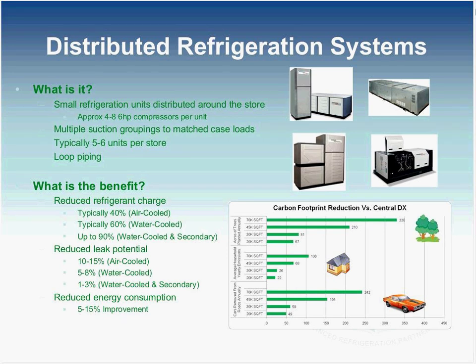redundancy, and also puts the unit closer to the load, reducing your refrigerant line runs, and can also provide some energy benefit as well. For a typical supermarket ranging anywhere from 40 to 60,000 square feet, the number of units can range in quantity, but we typically see anywhere from 5 to 6 units per store, and that would be displacing what would traditionally be used with 2 racks. These systems can typically be in loop piping, and as a result, you have some refrigerant charge reduction benefits as well. In comparison to a sized DX system, there are benefits in terms of charge reduction as well as leak potential reduction, which are the goals of the GreenChill Partnership.